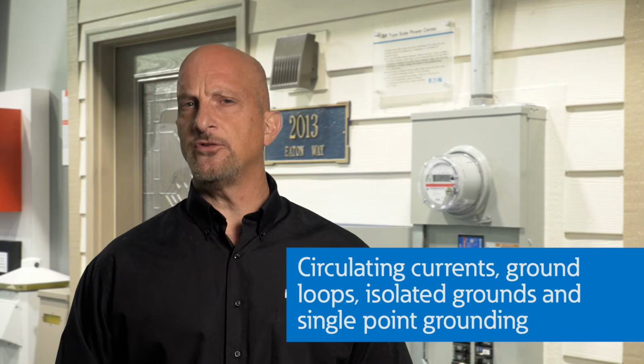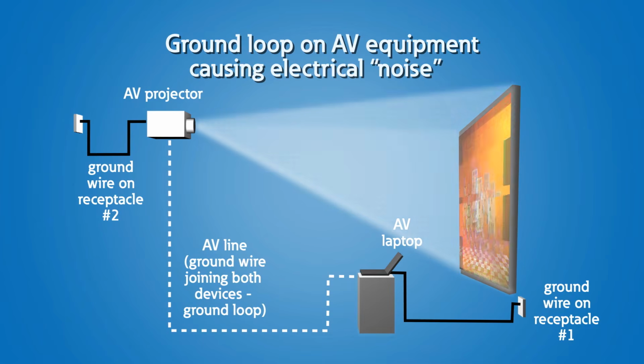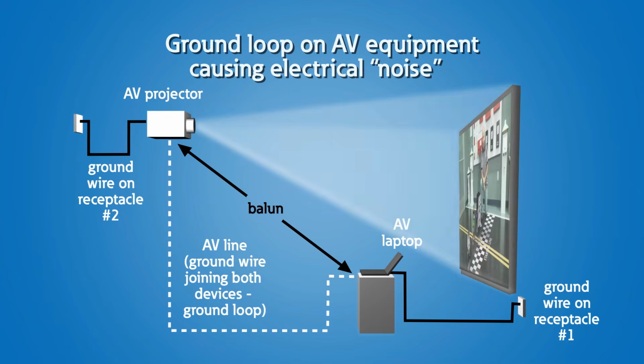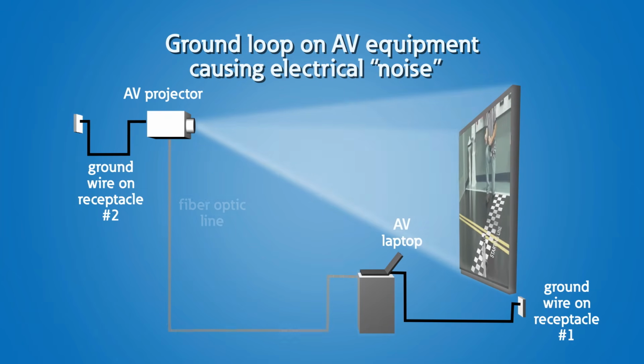This can be a slippery slope, and oftentimes it's problematic to force a system to have a single point grounding for quote-unquote sensitive equipment. I've seen plenty of situations where ground loops from AV equipment have caused electrical noise and must be eliminated, but there are well-proven methods for dealing with this situation.